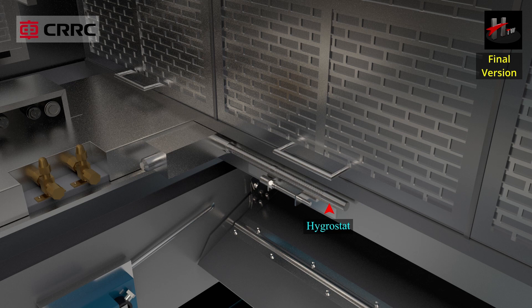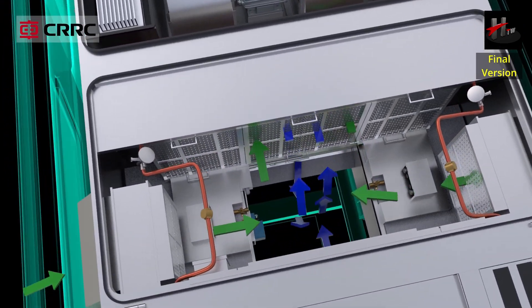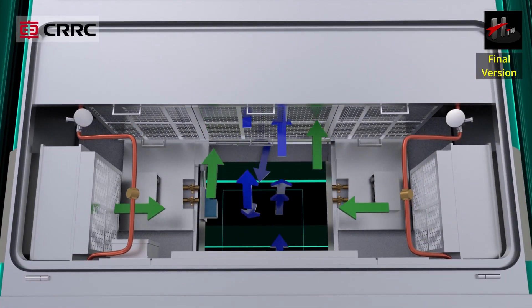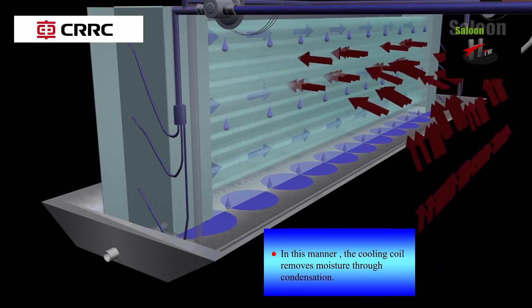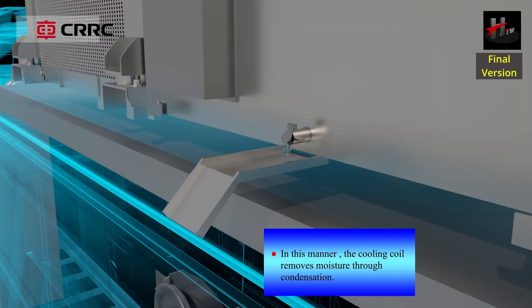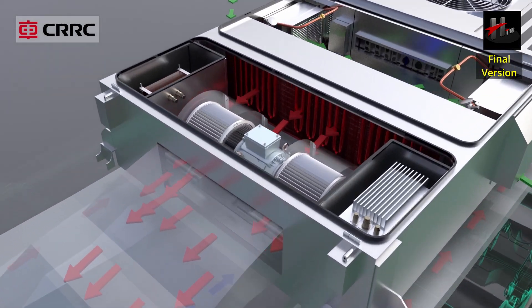When the Hygrostat signals that the relative humidity in the return air is high, one of the two refrigeration circuits is energized together with the heater bank. In this manner, the cooling coil removes moisture through condensation while the heaters prevent the saloon temperature from dropping.